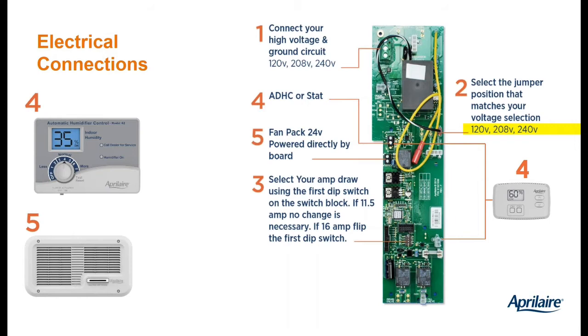What current do you have available? Do you have a 15-amp or 20-amp circuit breaker? That'll dictate whether you want 16 amps or 11.5 amps as your maximum — there's no reason not to pick 16 if your circuit breaker can handle it. Next, hook up the control — what's going to tell the steam humidifier to operate. Either our automatic digital humidity control, the model 62, or some other thermostat with IAQ abilities, a humidistat, or even a building automation system. We just need a dry contact to tell it to run.